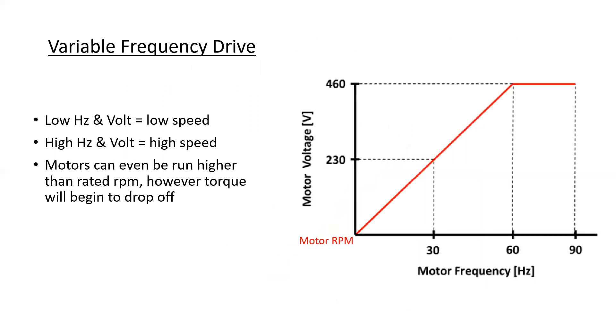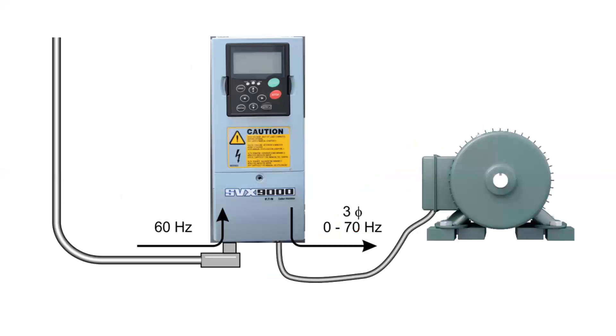At low hertz and low voltage, the motor will turn at a low RPM. At high hertz and high voltage, the motor turns at a high speed. Motors can even be run higher than the rated RPM; however, torque will begin to drop off. In this way, a VFD takes the nominal 60 Hz from the three-phase supply and provides three-phase output to the motor anywhere from zero to around 70 Hz, with specialty applications exceeding this.